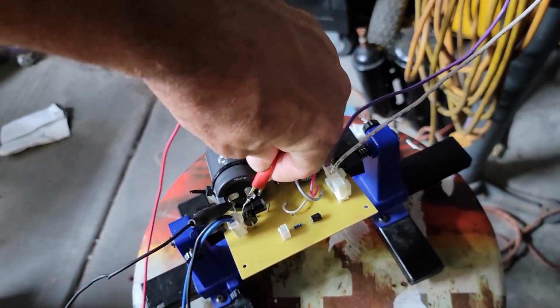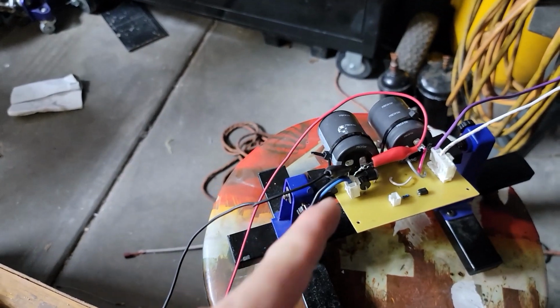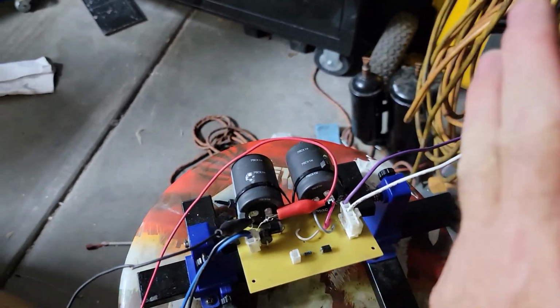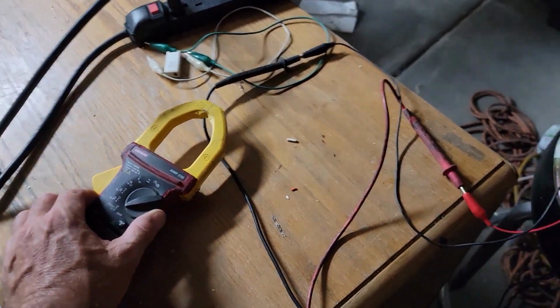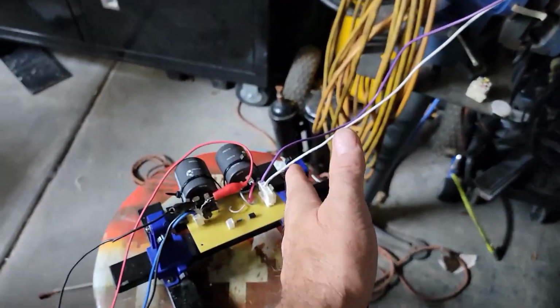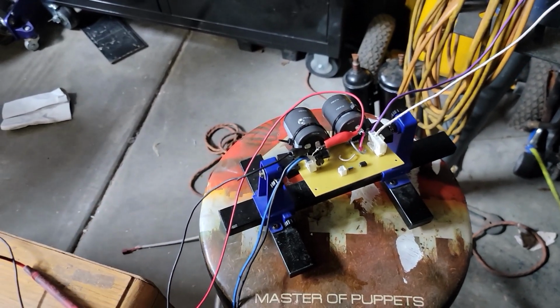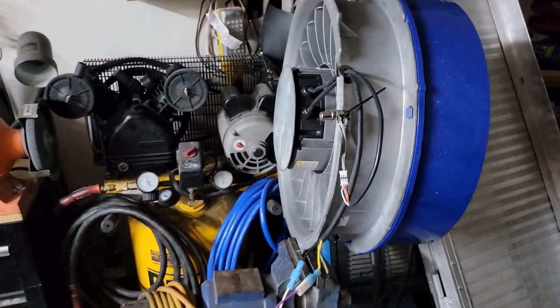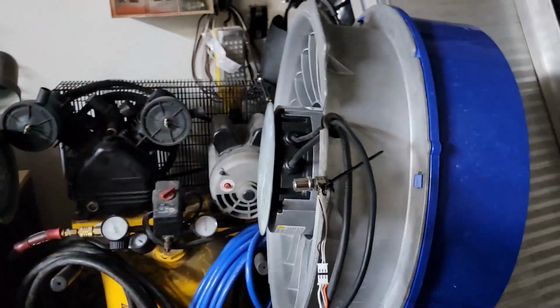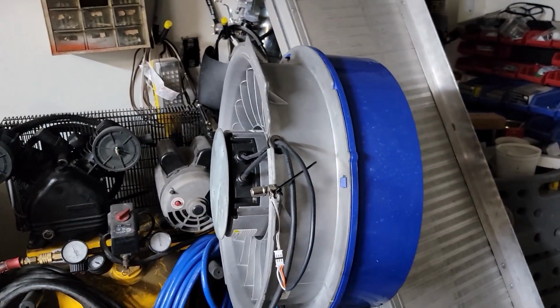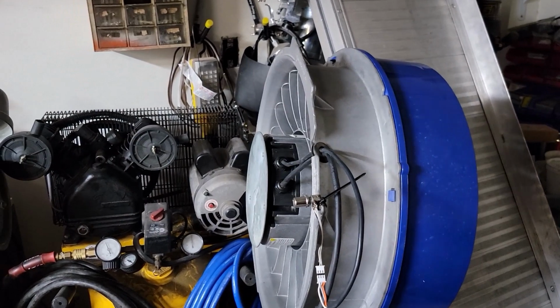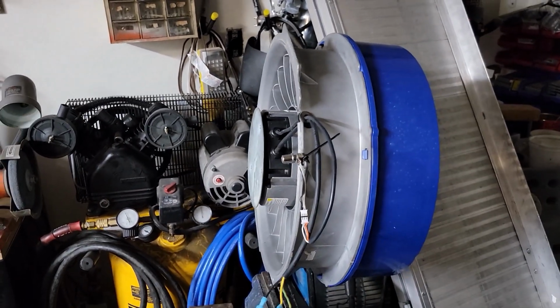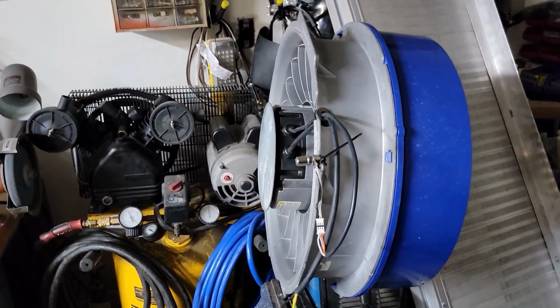But if anybody remembers my past videos, basically this is a simple voltage doubler. It works as long as it's AC voltage going in, and you step it up to a DC, rectified voltage. So you wind up getting the same rectified voltage in the end that you would with double the AC voltage. This is made for 208 to 230 volts single phase, and I'm sending DC voltage in, because I know, as the nature of these motors are, DC motors, they just go through a rectifier in there and it's charging capacitors. So if you send DC in, it doesn't matter what polarity it is, it'll just go through the diodes and the end result's the same. You can charge capacitors in there.